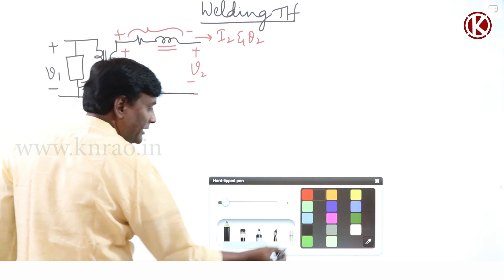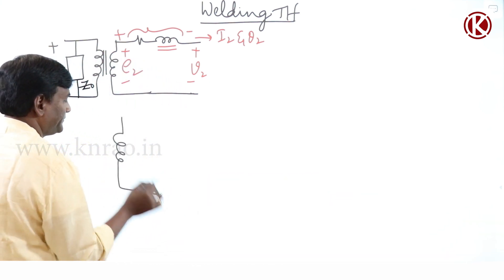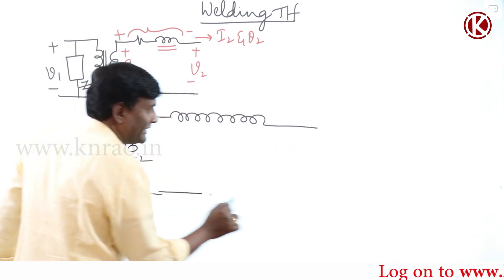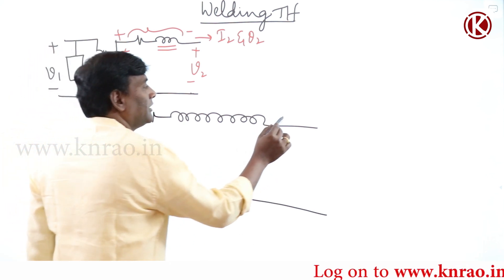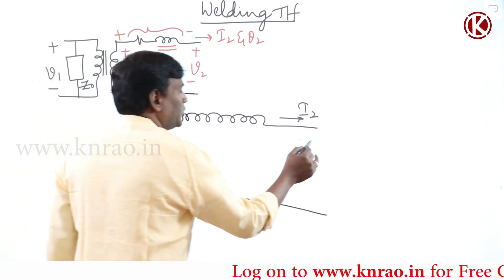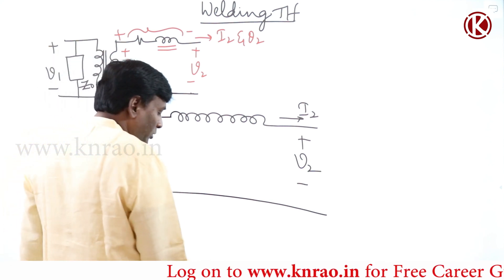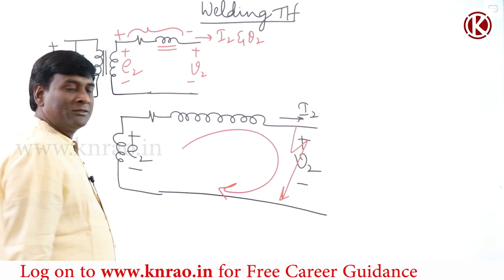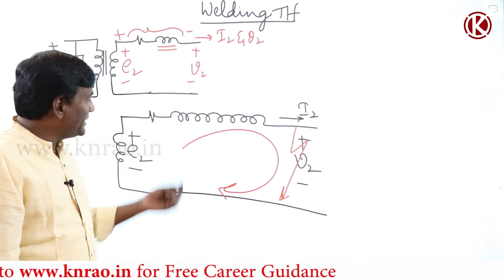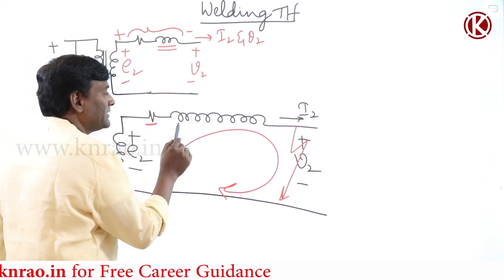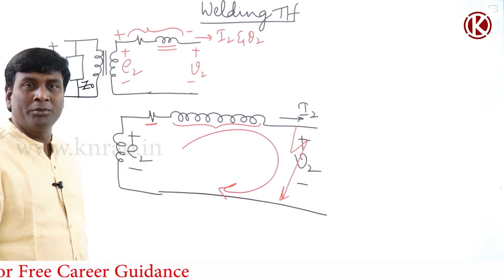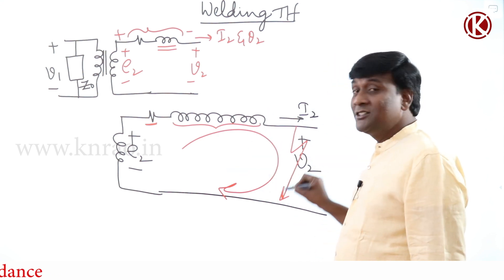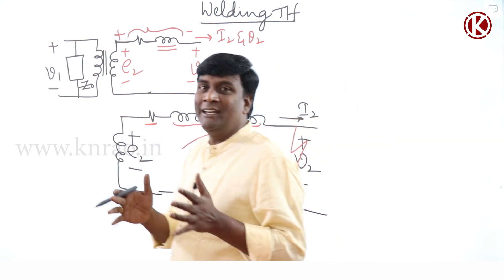Consider the secondary circuit: e2 with resistance and leakage reactance. When i2 is zero, e2 equals v2. Even if a short circuit occurs, the short circuit current is e2 divided by z, which will be limited if z is high. Impedance can be increased by raising resistance or leakage. Increasing resistance makes it lossy, but increasing leakage is lossless. So by increasing leakage, steady short circuit currents can be reduced.